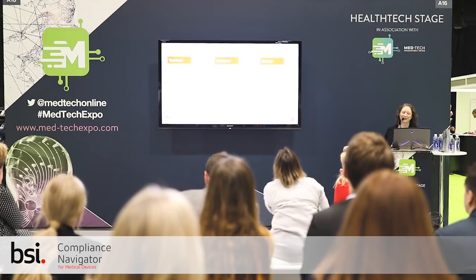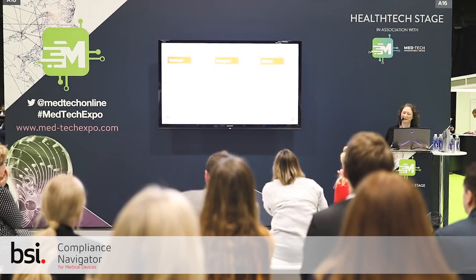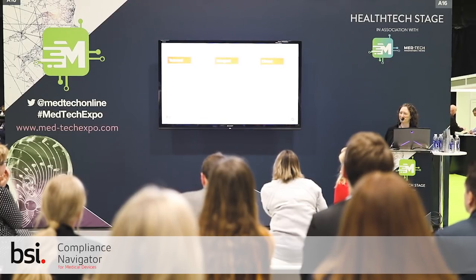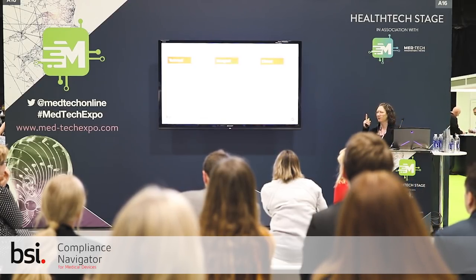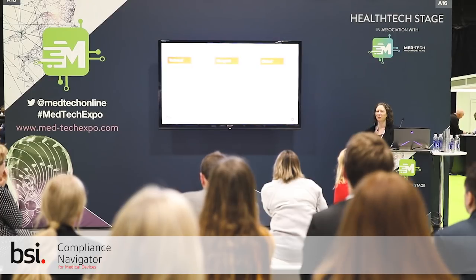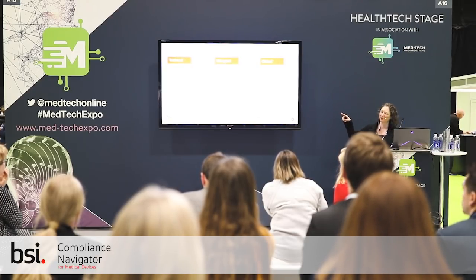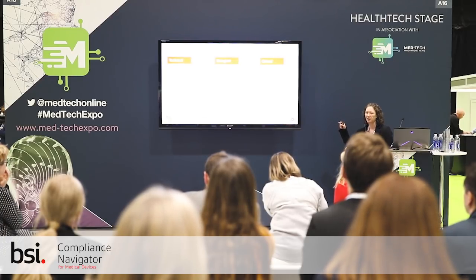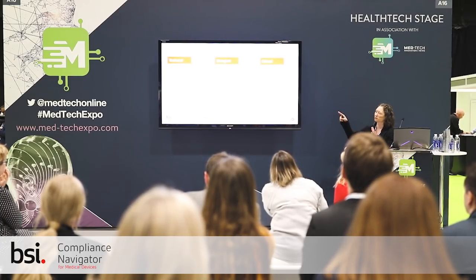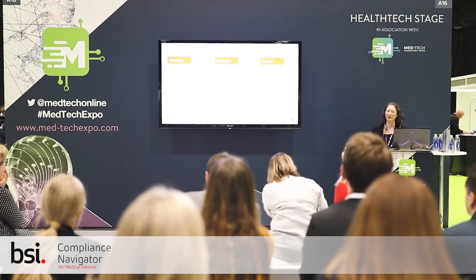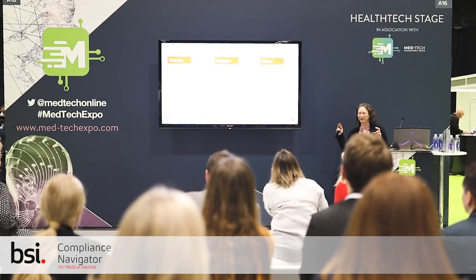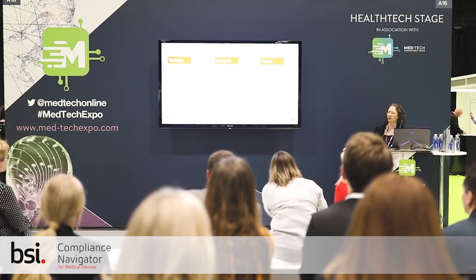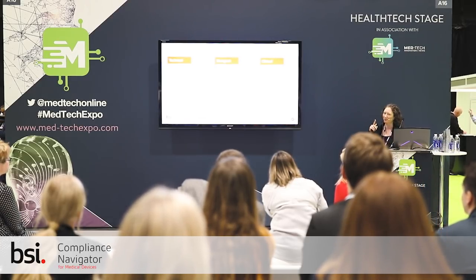And it does say that each device with an equivalence claim must have full clinical, technical, and biological characteristics. So we're talking about one equivalent device. We're not talking about an equivalent device technically and another equivalent device biologically and another equivalent device clinically. We're talking one device that meets all of those requirements. So there's no Frankenstein, I think is what the MHRA call it, no Frankenstein approach to clinical equivalence. It has to be one device.